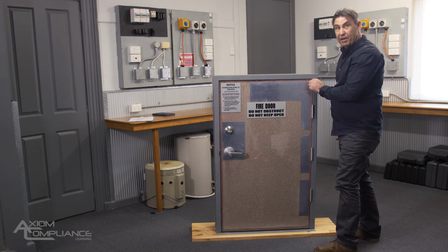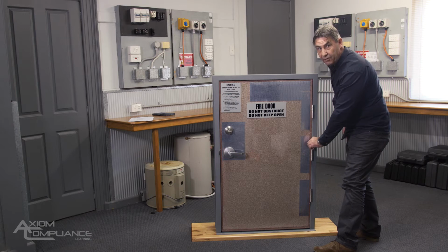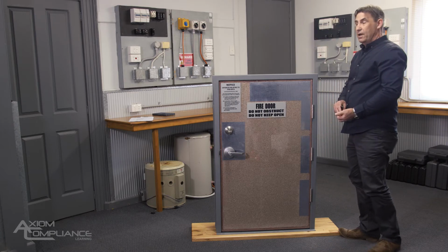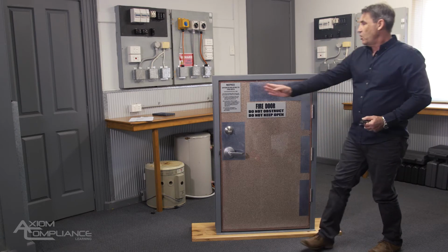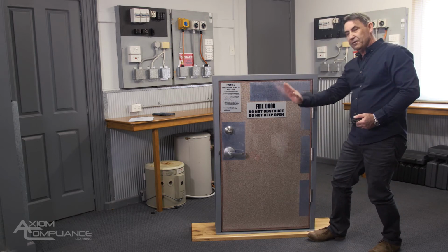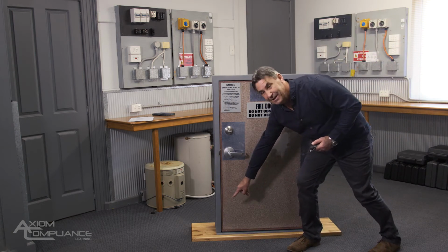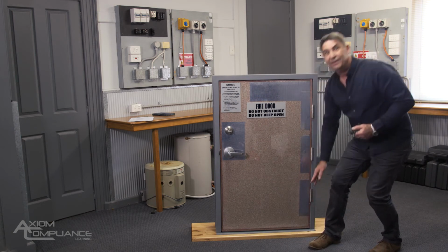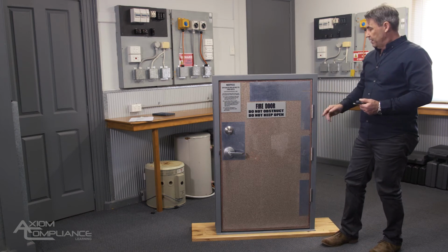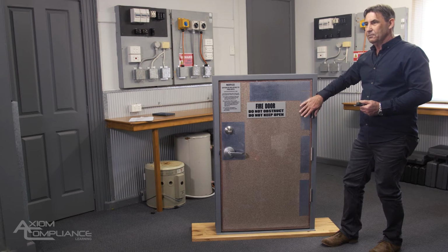It's getting to around about 4 millimeters. And as I come down the door, I'll see that it gets tighter again. What you'll notice is that it's tight up here and loose over here, which means the door is starting to fall this way. And you'll see that it'll be looser down there and tighter down here. Which is very typical of fire doors. The hinges start to move forward and it changes the state of the door.